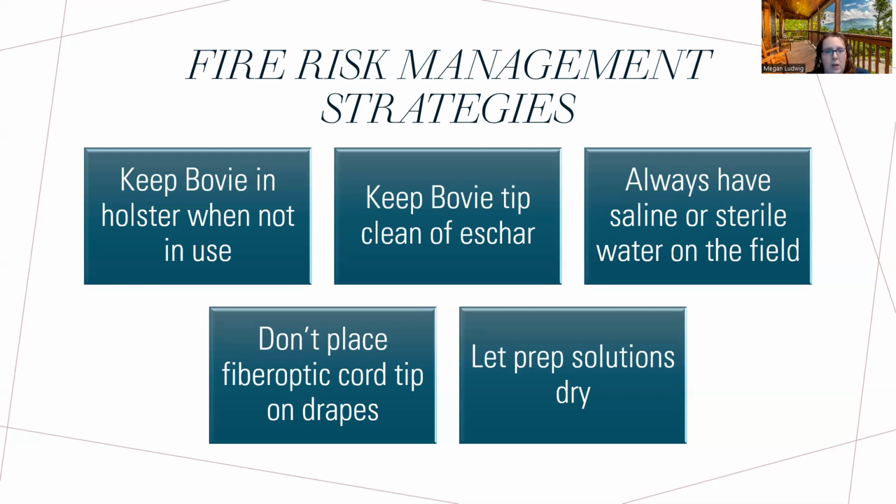That could fall back to you as negligence, because you need to watch for that and put it back in the holster. You also want to keep the bovie tip clean of something called eschar, which is after you use the bovie a lot and it burns through the tissue. Sometimes the tissue can get built up on the tip of the bovie, that's eschar, that burnt tissue. So if you're using a non-coated bovie tip, which some places still use, you'll need a bovie tip cleaner, a little cleaner pad. It's kind of rough. Otherwise, you can keep it clean with a lap pad or a towel or something. Just wipe that bovie tip off. Otherwise, you can start a spark.